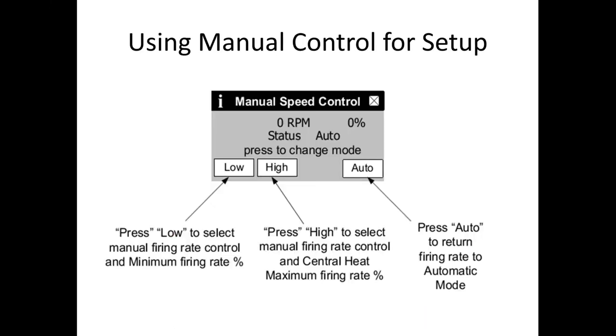Manual control. This is really only going to be used for setting up the boiler, for doing our combustion testing. One of the things we want to do when we're doing our combustion testing is dissipate heat. We're going to need to have this boiler run in high fire at its max BTU range for up to 15 minutes. In some cases, we're just going to open up the auto feed and run cold water through the boiler.